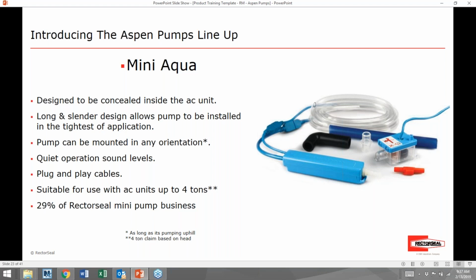We do this for versatile installation options. You can place the pump where it needs to go, and then you can route the wires to the terminal block of the indoor unit to wire it up. Or you can wire it up first and then route the cables to the pump. Just gives a little added flexibility in installation. Again, the Mini Aqua is also suitable for up to 4 tons based on head or vertical distance of pumping.